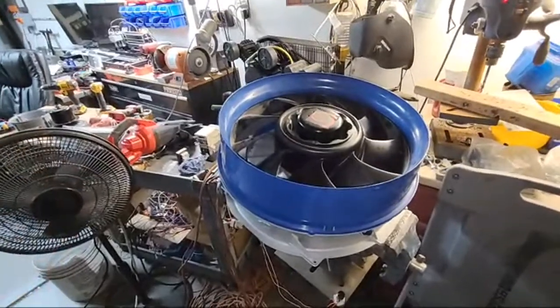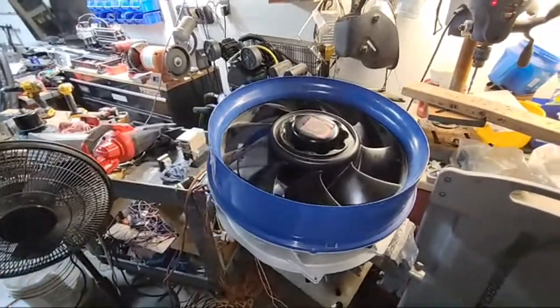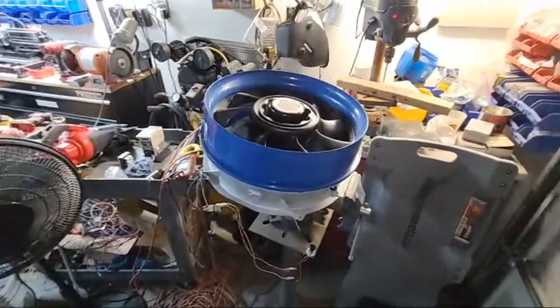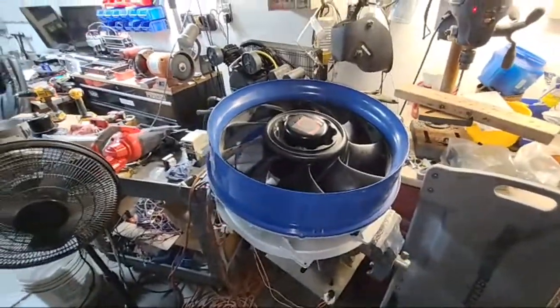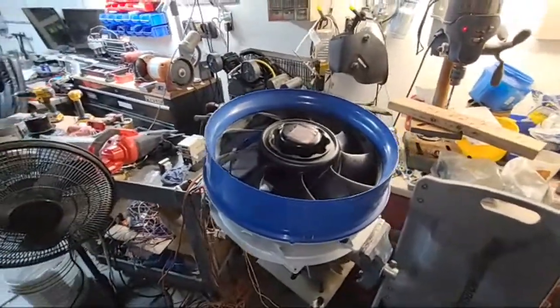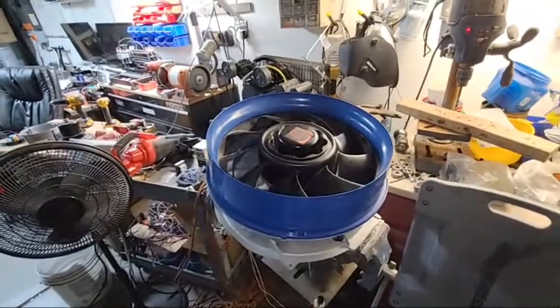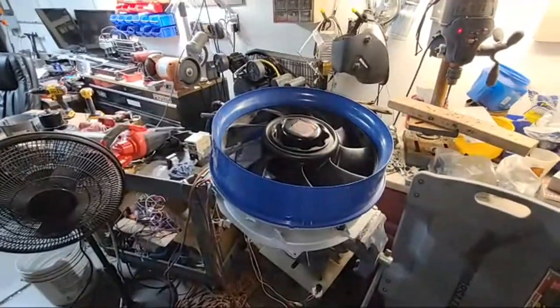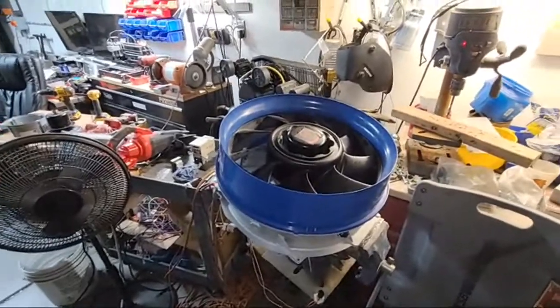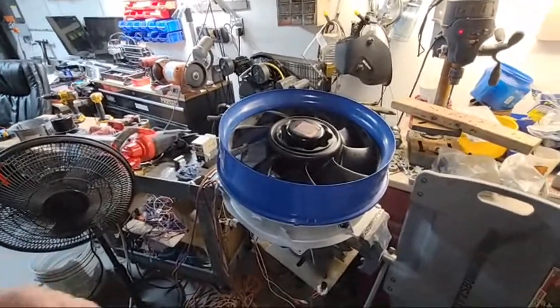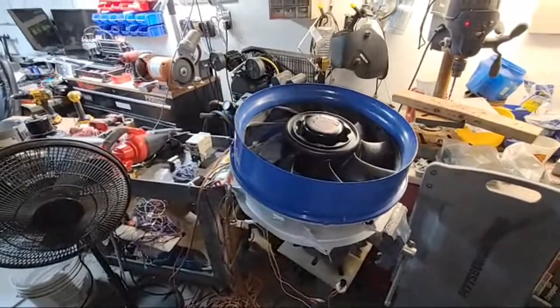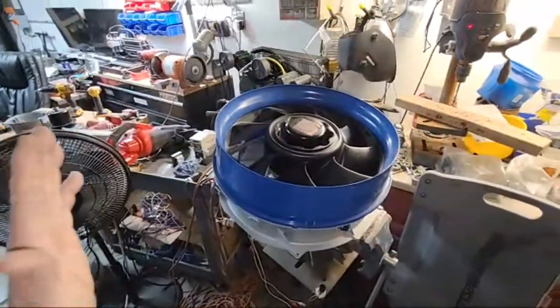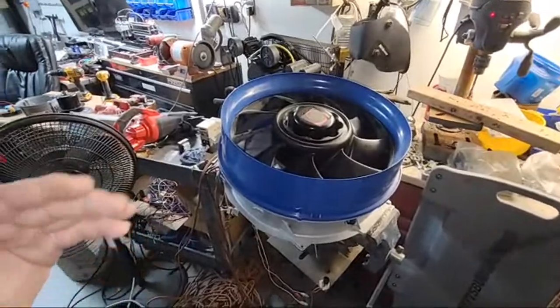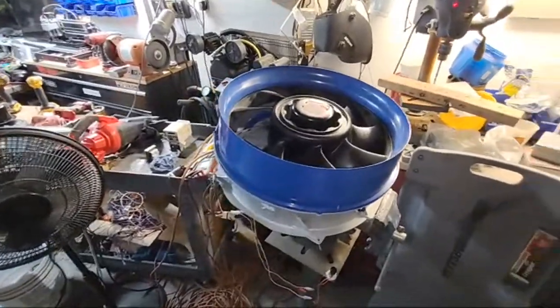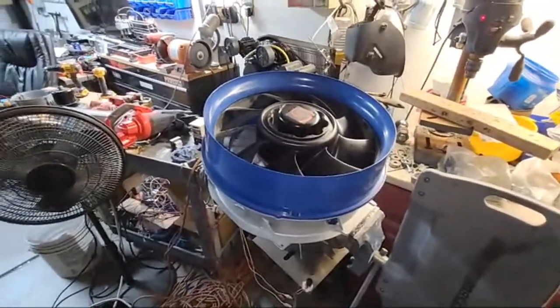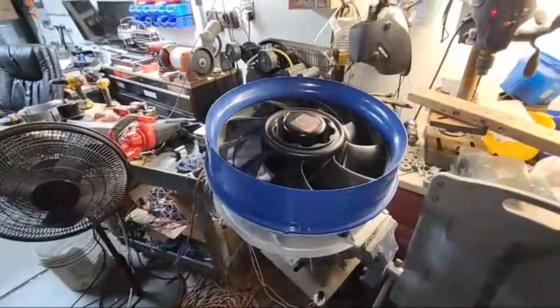And guess what? We've had to pull out like 4 or 5 ounces out of a 4 or 5 ton, and then it was fine. But if you didn't, they would stack up and trip. And what happens is when you first run them, the real critical part is you've got to let the space cool down and wait for that load to drop so the thermal expansion valve starts throttling back, pinching off. Then you get a higher percentage of refrigerant in your outdoor coil than you had when you started up with a high load.